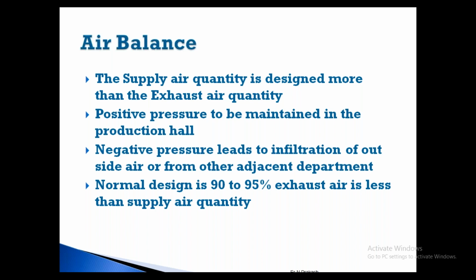Whereas the exhaust system will be mostly an underground exhaust system, through the floor grills and slit grills, as well as machine exhaust. We have pneumafil exhaust. We have technology air in the OE machines. You have compact air. All this air will be taken through ducts and collected in underground trenches. The underground trench is connected to a rotary filter, cyclone system, and again to an exhaust fan. So between this supply air quantity and exhaust air quantity, there should be a slight difference.